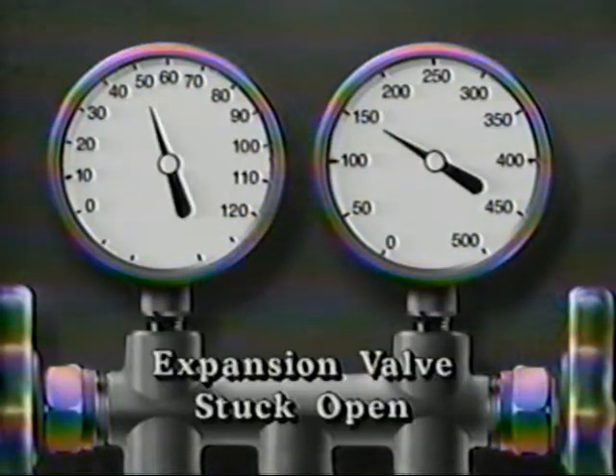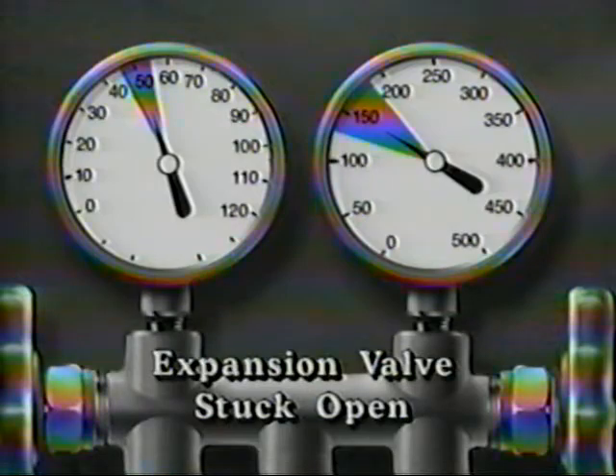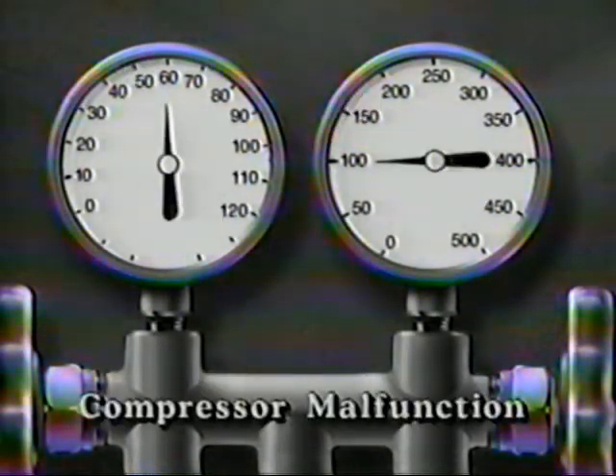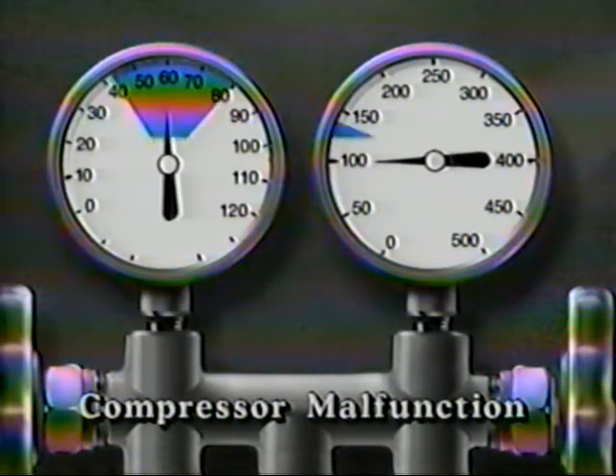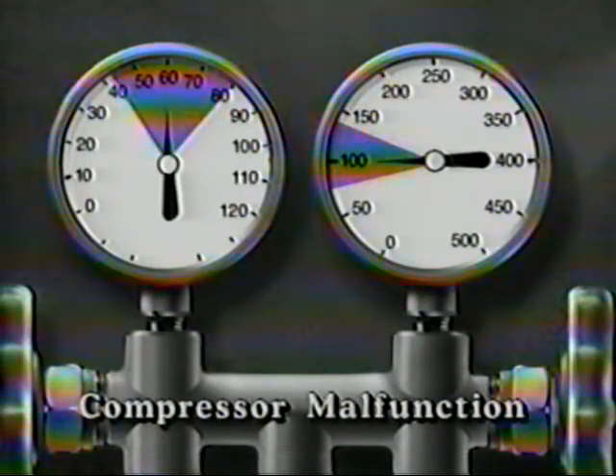If the expansion valve is stuck open, causing flooding of the evaporator coil, the suction pressure will be high, while discharge pressure will be low. The expansion valve must be replaced. If the belts are loose or worn, if the compressor clutch isn't working, if there's an internal leak in the compressor, or if the pressure switches are not working, pressure on the suction side will be high and pressure on the discharge side will be low. Belts, engine drive pulley, compressor, clutch, or pressure switches must be replaced as needed.